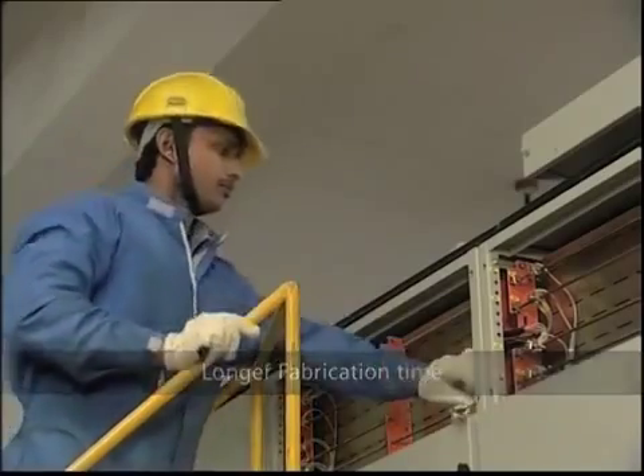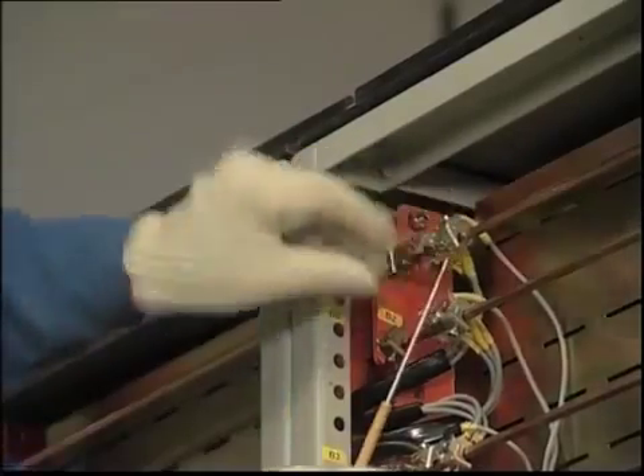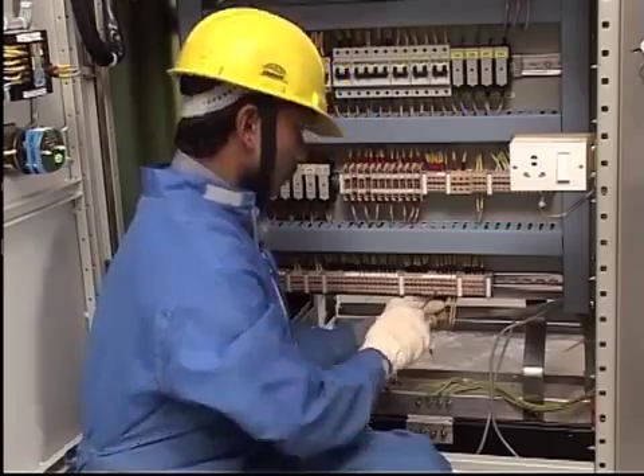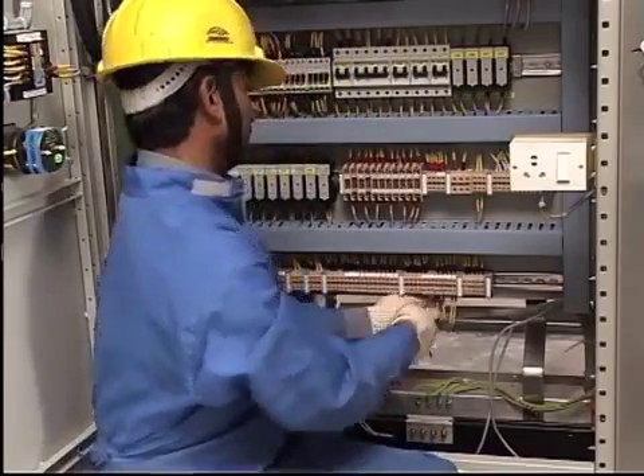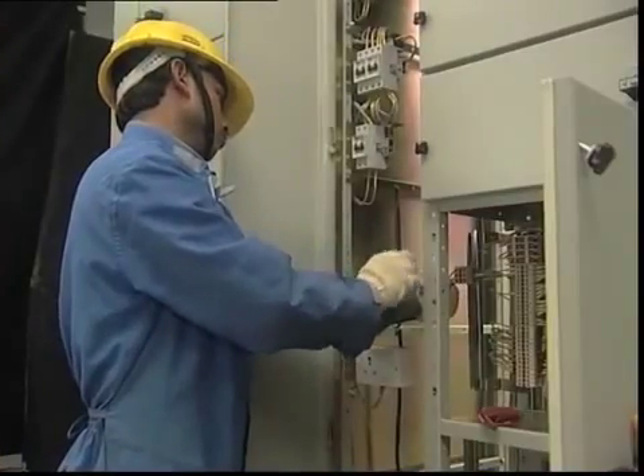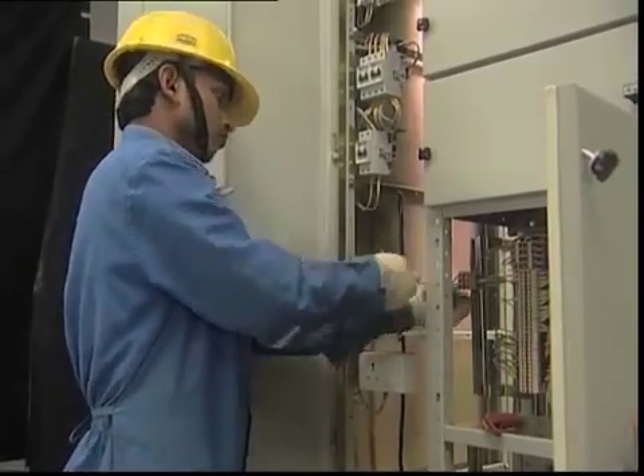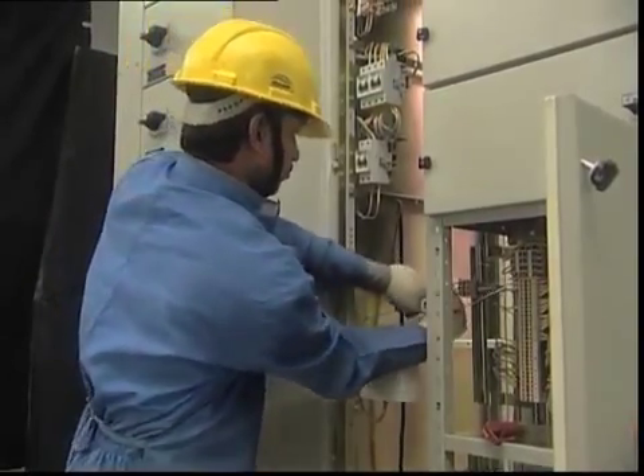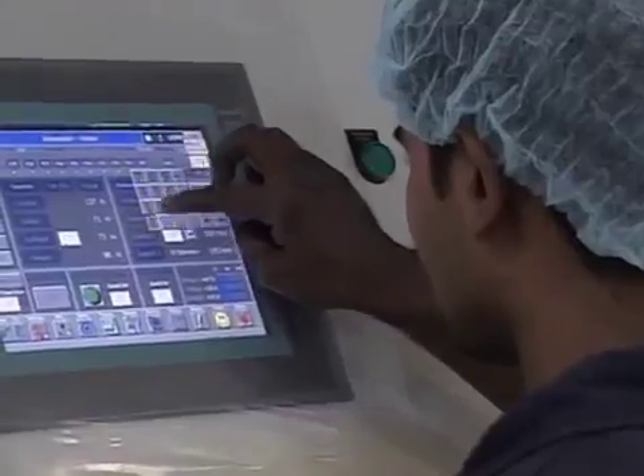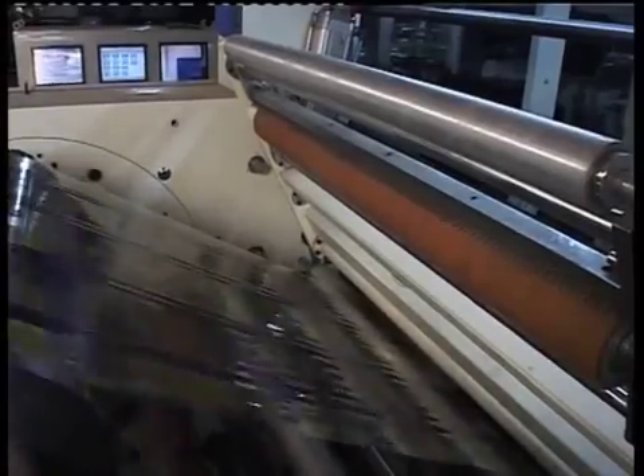Longer fabrication time. Due to normal requirement as well as last-minute changes during drawing approval, accessory fitment in the workshop of the panel manufacturer is required. Long and complex process of accessory fitment for each breaker increases total manufacturing time.